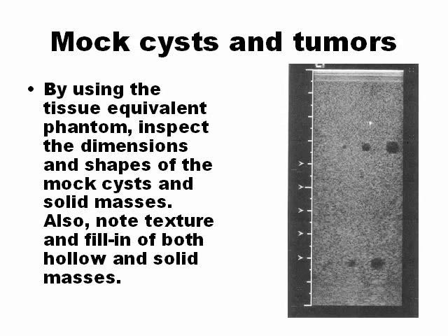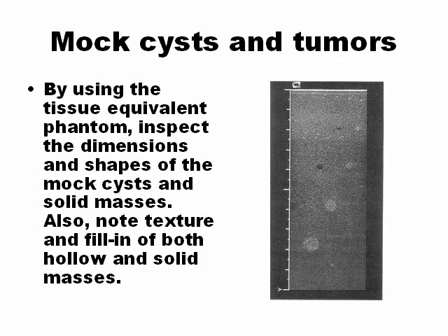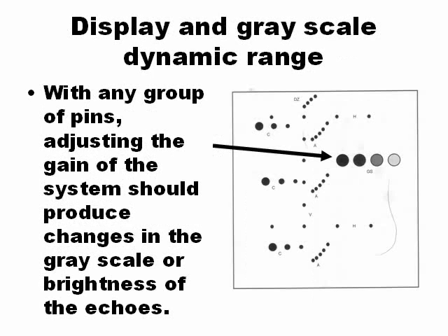Phantom with mock cysts and tumors. By using a tissue equivalent phantom, you can know the dimension and the shape of cysts or solid masses, also the texture of the tissue. You can see here tumors and cysts in this phantom. Display and grayscale dynamic range. With any group of pins, you can know if the contrast of the machine is accurate and if the grayscale is the same as you expect.